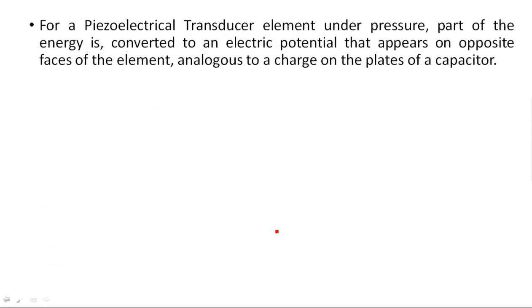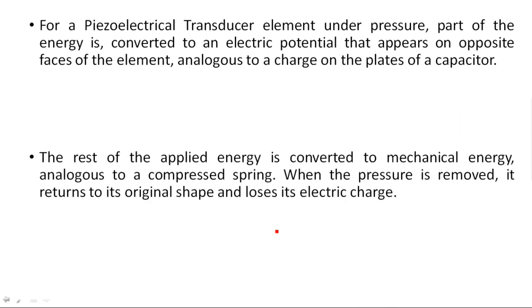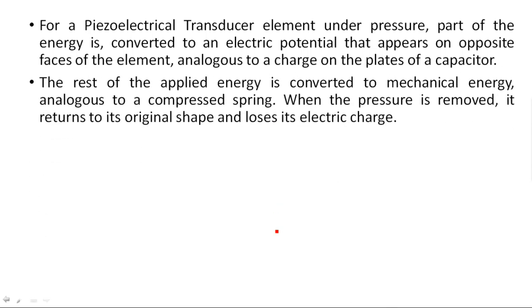For a piezoelectric transducer element under pressure, part of the energy is converted into an electrical potential that appears on the opposite faces of the element, analogous to charge on the plates of a capacitor. The rest of the applied energy is converted into mechanical energy, analogous to a compressed spring. When the pressure is removed, it returns to its original shape and loses its electric charge.